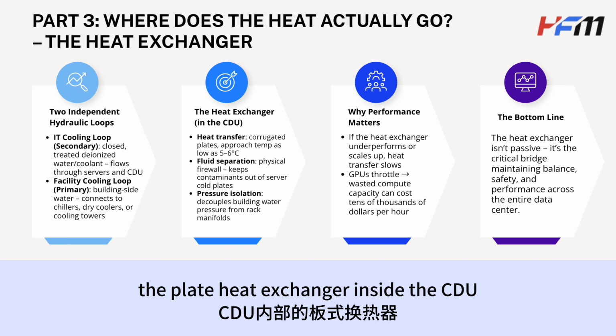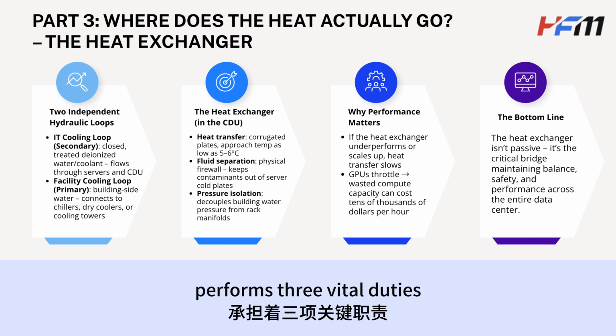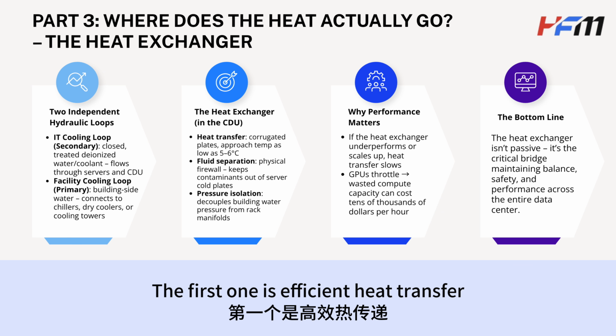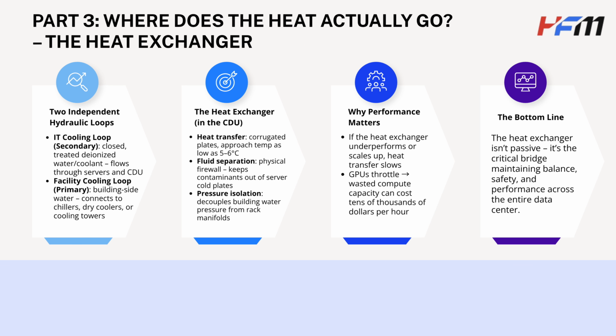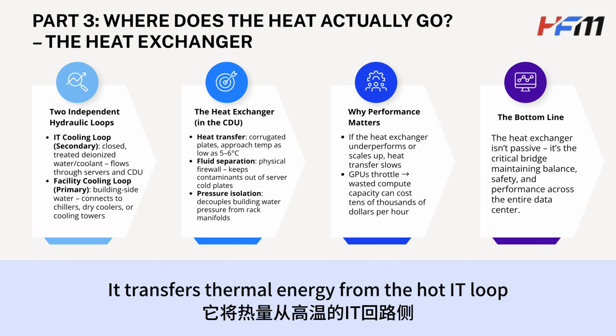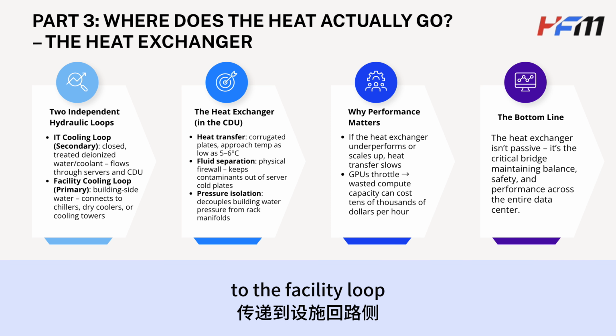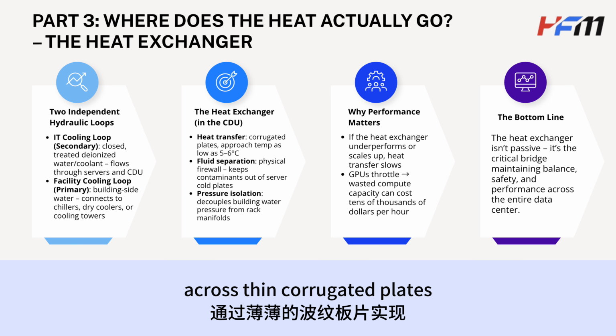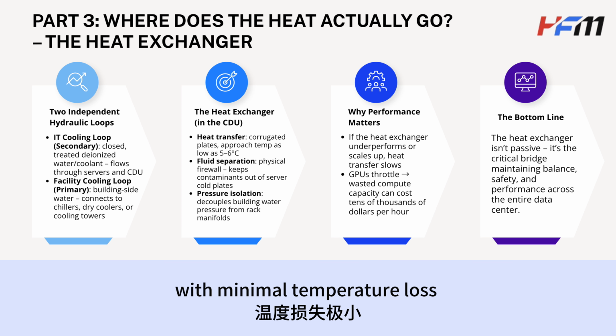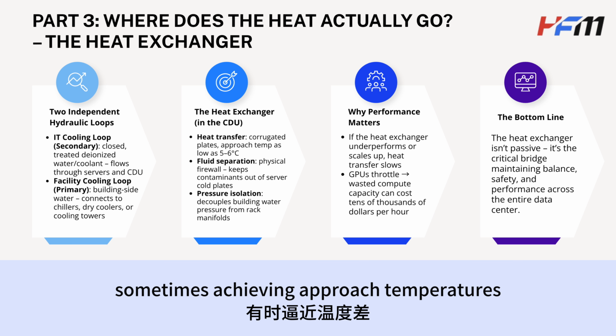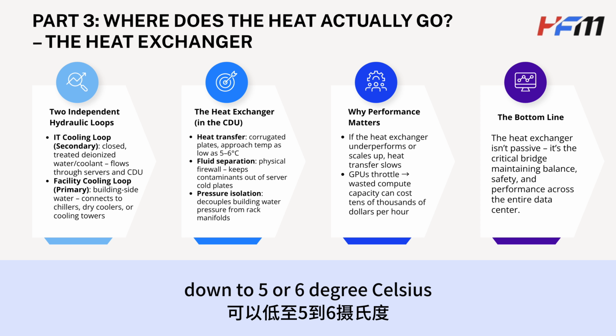Exactly. The plate heat exchanger inside the CDU performs 3 vital duties. The first is efficient heat transfer. It transfers thermal energy from the hot IT loop to the facility loop across thin corrugated plates with minimal temperature loss, sometimes achieving approach temperatures down to 5 or 6 degrees Celsius.